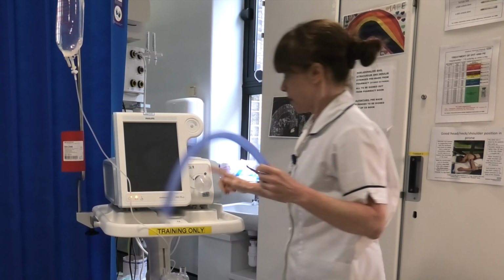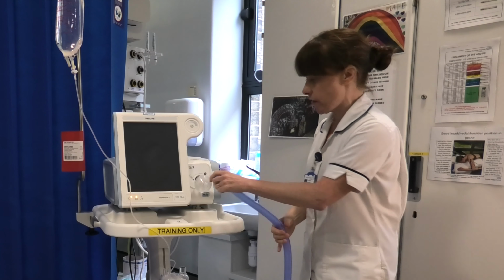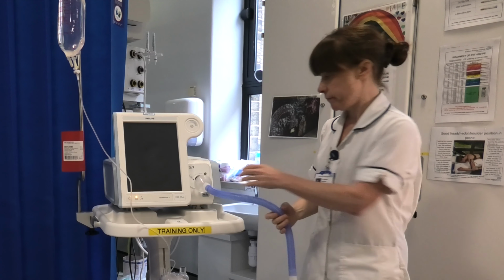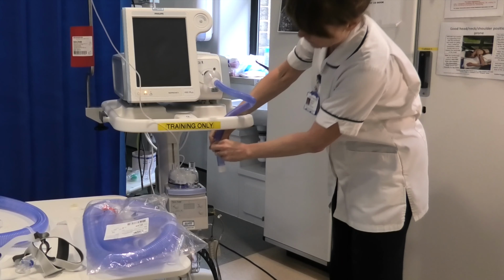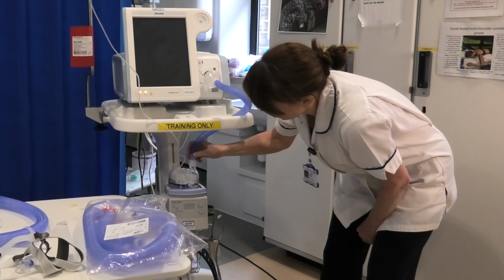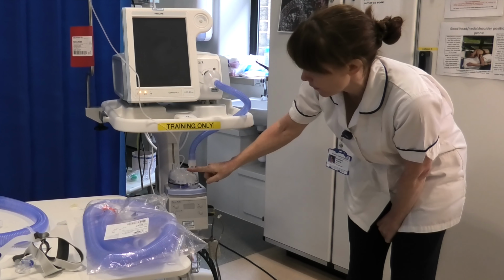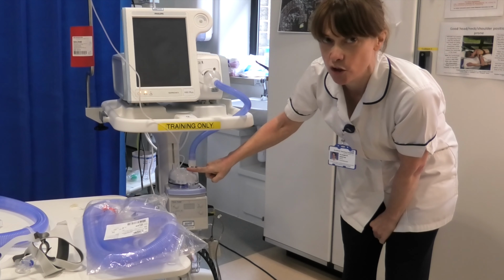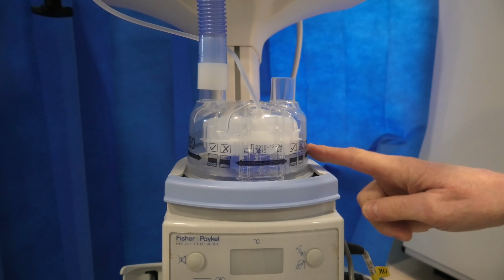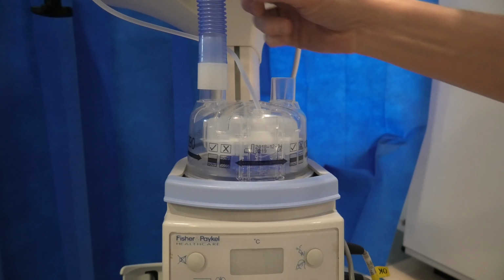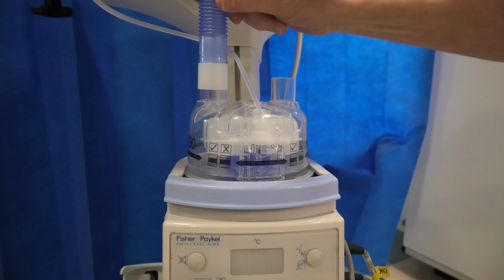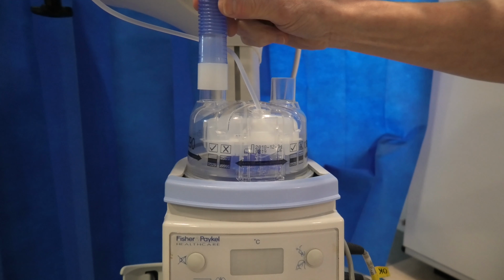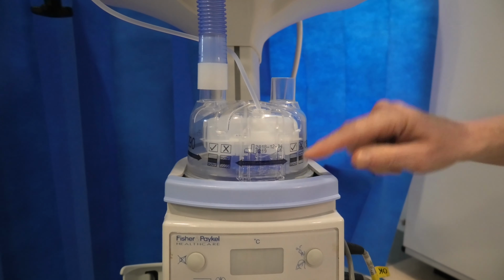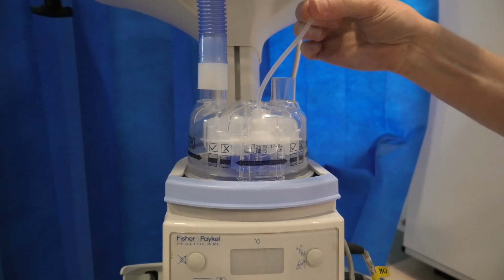Then we need to get the gas from the ventilator into the humidifier. So we use the short tubing on the filter into one side of the chamber. It doesn't matter which side of the chamber you use, either's fine. So if we look at the Fisher-Paykel humidifier, you can see that we've got our tubing which is coming via a filter from the ventilator into the chamber, into which we've got sterile water running, which runs into here.